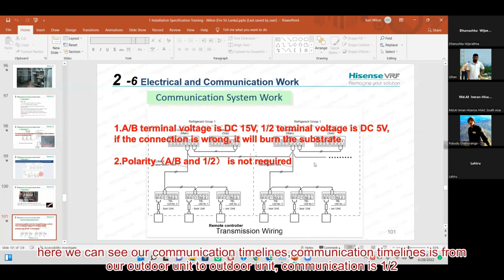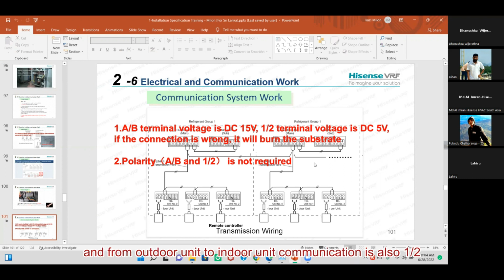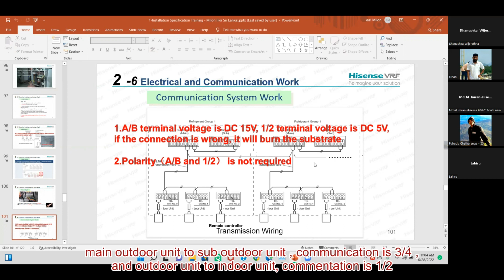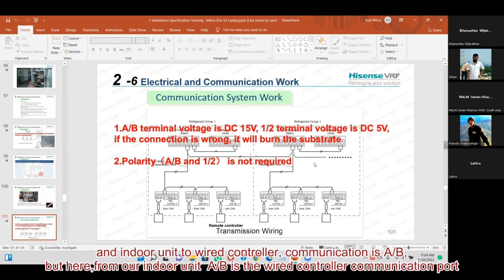Here we can see our communication terminals. Communication from outdoor unit to outdoor unit is 3 and 4, and outdoor unit to indoor unit communication is 1 and 2, and indoor unit to wire controller communication is A and B.